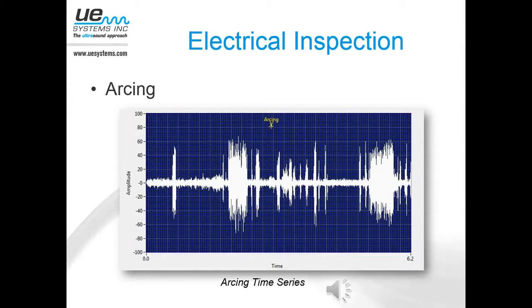That is an extremely severe condition. If you hear that or something similar coming from enclosed switchgear or your substation, failure is actually occurring, and not only is it dangerous, but you're risking an explosion and severe damage to the assets. That's something where you want to shut it down and find somebody immediately. That's sort of a code red when you hear that type of sound using ultrasound for electrical inspection.